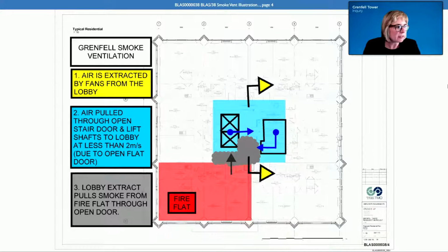Well, if I continue my analysis - we've got smoke with its momentum flowing across the corridor. What you're then doing is interrupting the flow of this momentum with your extract system in both locations, extracting away. This question of depressurization needs to be separated because it's a different system. You're extracting smoke from the fire room, and you're extracting smoke from the lobby. This is the fundamental principle of this type of system - you're stopping the smoke approaching the stairway, and extracting it.